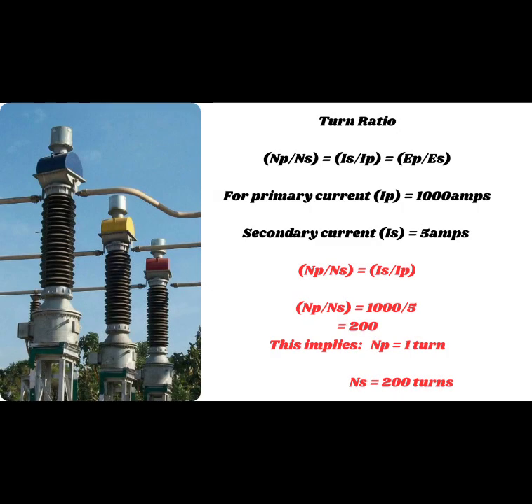For instance, if a current transformer is built to monitor a 1000 amps primary current, the turns ratio would be 1000 is to 5. This implies the secondary must have 200 turns. So this is how the winding configuration is made to meet up the required current expectations.